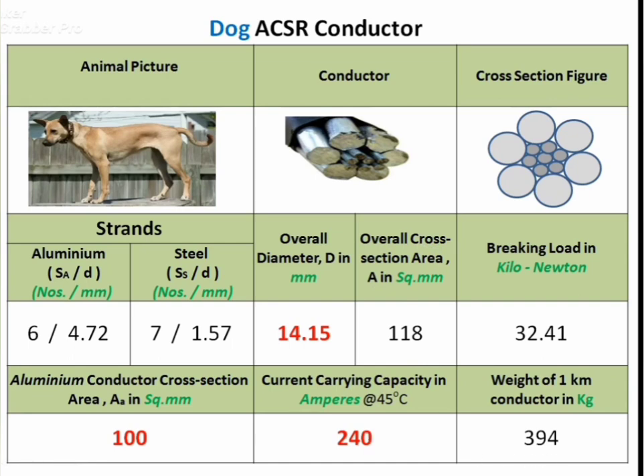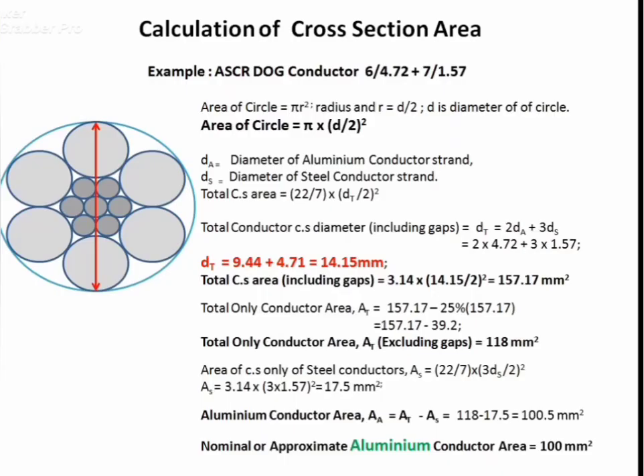Remember: total conductor area is 118 mm² and only aluminium area is 100 mm². Current carrying capacity is 240 A and weight of 1 km conductor is 394 kg. Now we will see how the aluminium conductor area is calculated. Six aluminium strands with diameter 4.72 mm and seven steel strands with diameter 1.57 mm are taken as the example of Dog ACSR conductor.